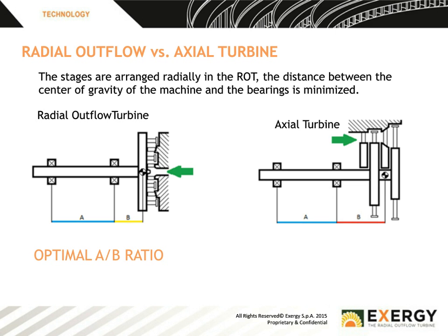If we look first of all at the radial outflow turbine, this gives you a clear explanation of how it works. You've got the fluid coming in centrally, axially, it's then turned radially, it then expands out through the stages on a single disc. You'll notice that we've marked the center of gravity and the distance from the bearings. So in organic Rankine cycle systems, the unit is always overhung, which means the bearings are on one side of the disc.